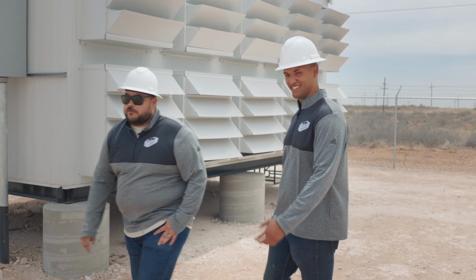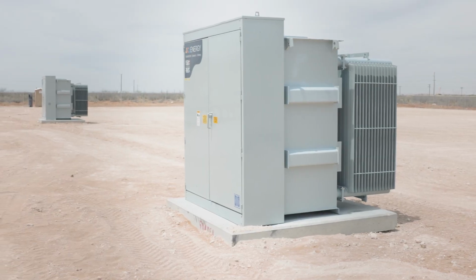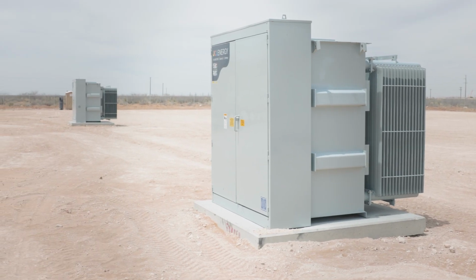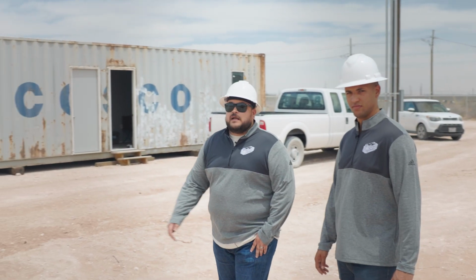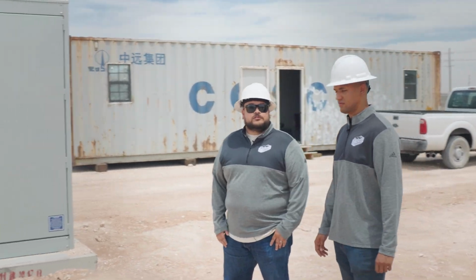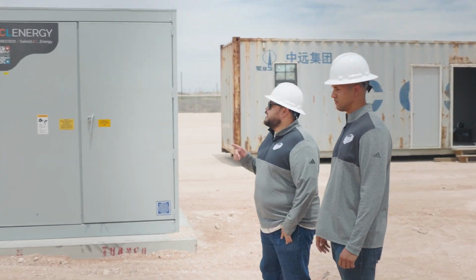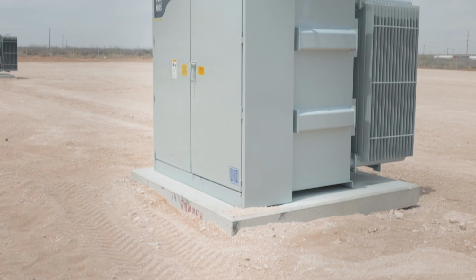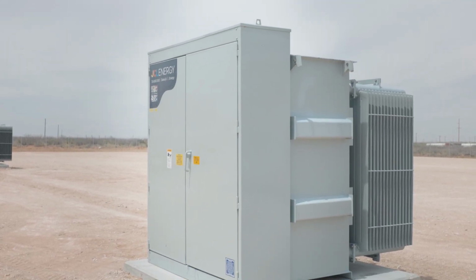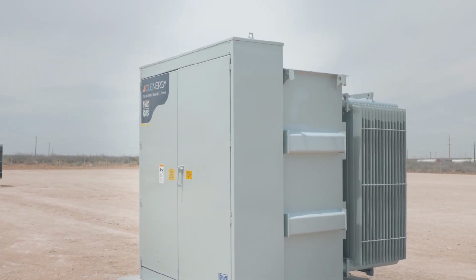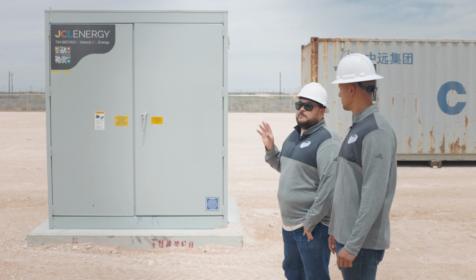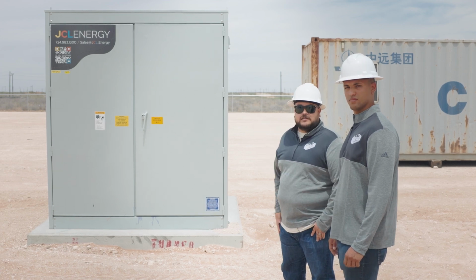Right behind you, we have one of our transformers. So we have 3 transformers on site. This site is a total of 5 megawatts right now. It's going to be expandable to 15 megawatts. Each one of these transformers is 2550 kVA, connects to 2 containers each. Each one of these containers is about a megawatt. And so each transformer is running about 2 megawatts worth of power connected to each one of these containers.